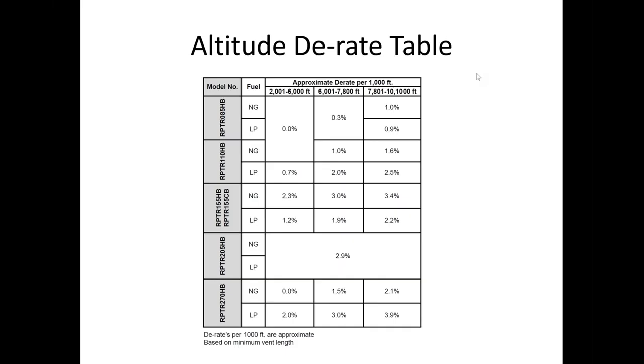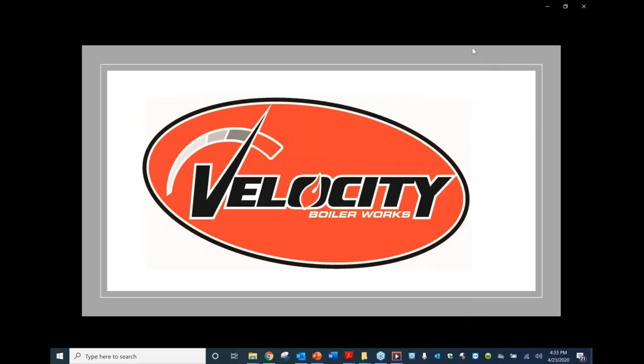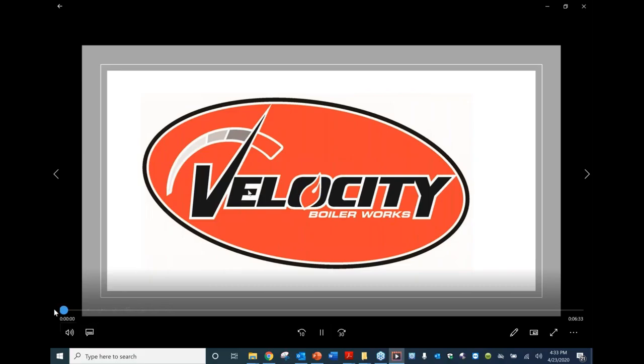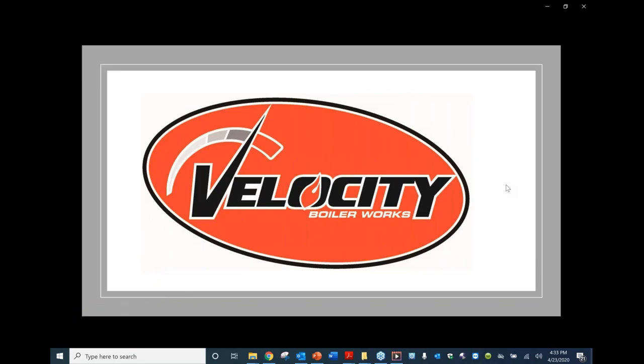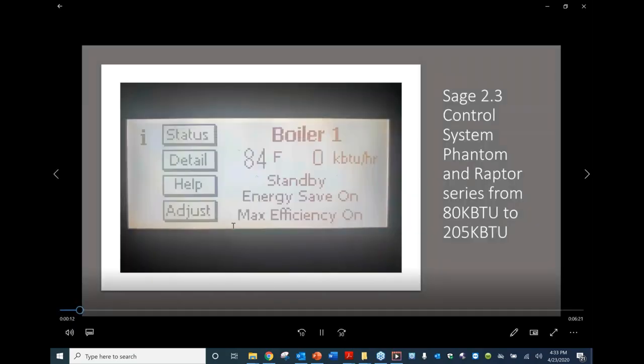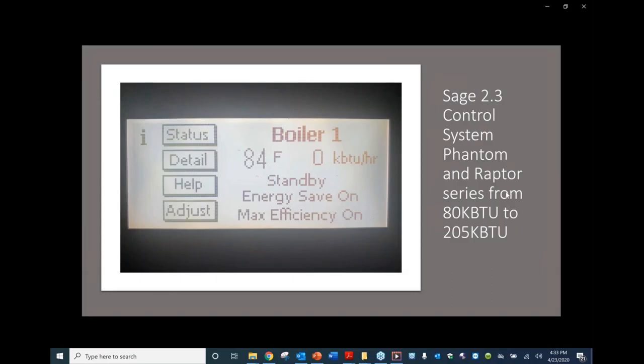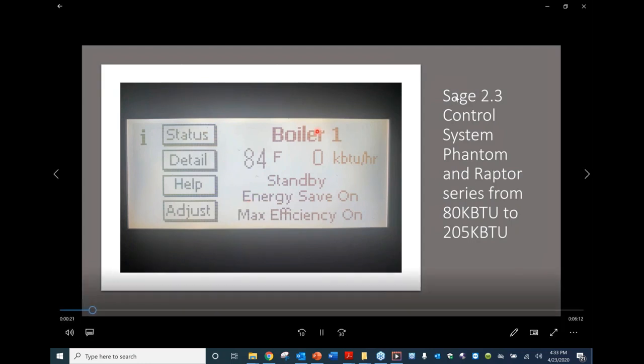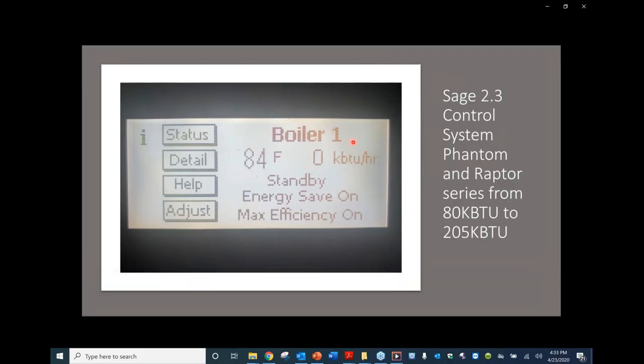In this training, we're going to cover the Sage 2.3 control system and setting the product up for altitude and proper fuel. The home screen on all our boilers is going to look like this. You're going to have your status, your detail, your help, your adjust. It'll say boiler, current supply temperature, and the BTUs.